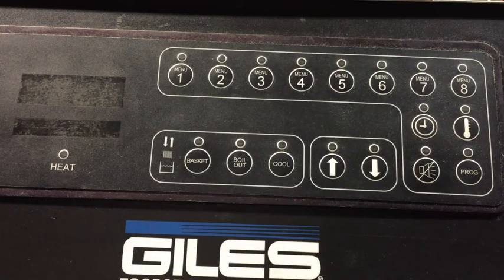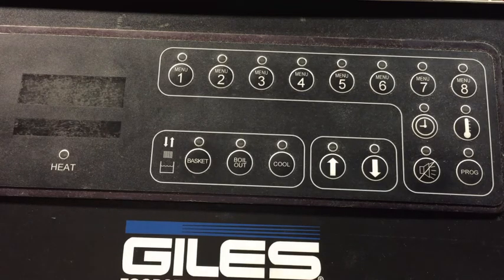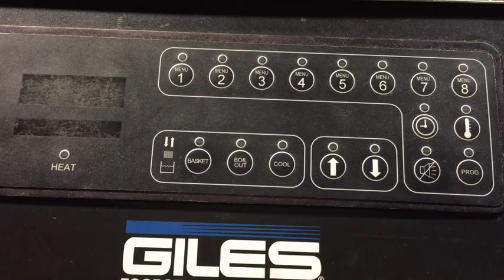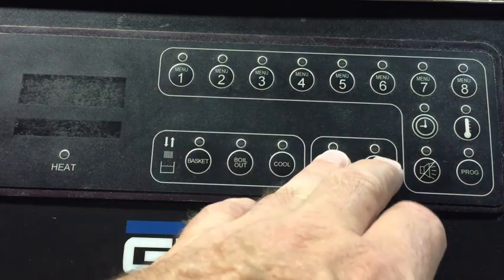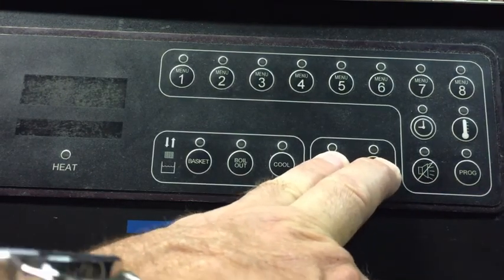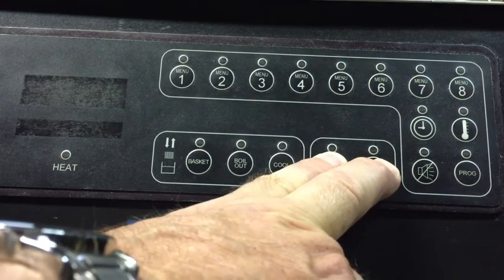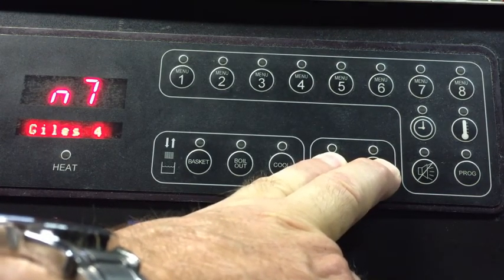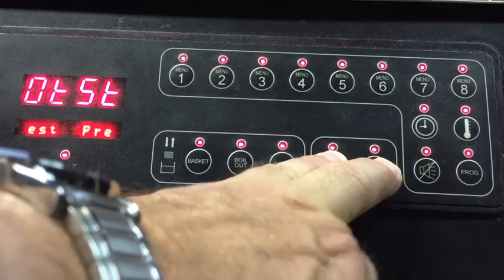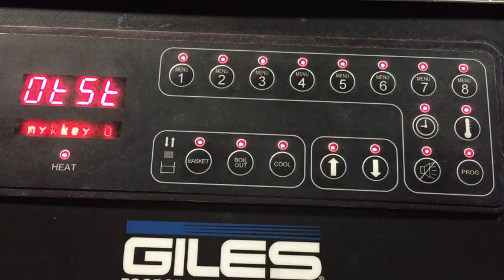Now we have limited diagnostic capability with the older N7, but one thing that is very valuable and comes into play quite often is the keypad test, and I'm sure you'll want to use this one. What you'll do is, with the unit in the off position as shown, press and hold the up and down arrows at the same time while turning on the power. Hold those two buttons in until it completely boots up, and you'll see it says OTST. If it had gone to hold or ready or any other display, you would have had a problem with the keypad because it wasn't seeing the keypad presses of the up and down arrows.